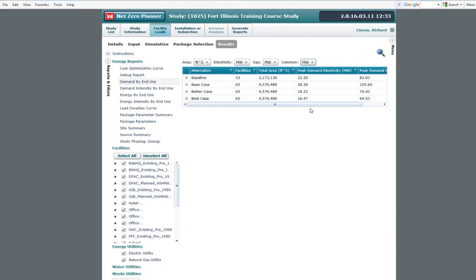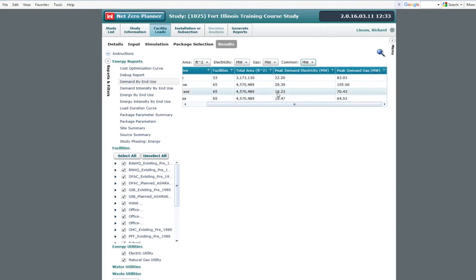That study area is seeing. So we can see that right here. And in this case, if we built the buildings better, we actually reduce our peak. We reduce it from this 22 megawatts down to 18 megawatts, and that can be a big deal in making decisions if you can build more structures, if your infrastructure will allow it.